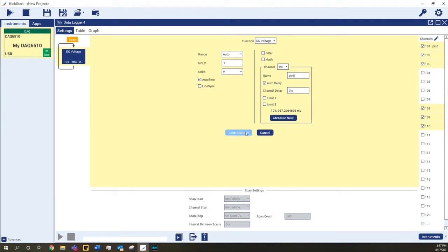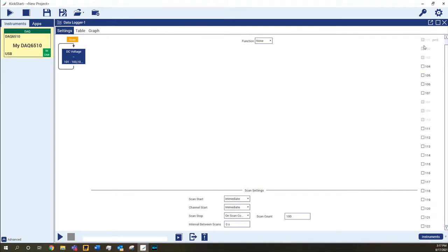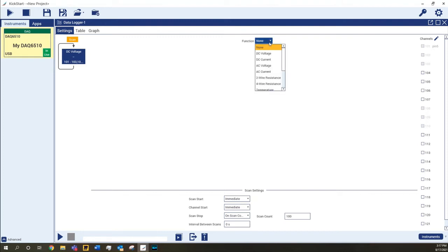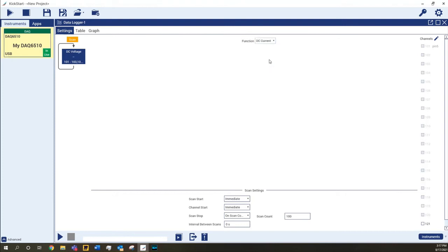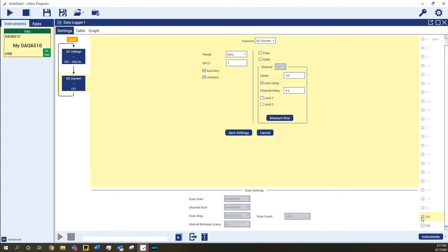Once you've configured the group, save the settings for the configuration, which closes that block. Notice that the configured channels are no longer selectable, as they can only be configured for one measurement at a time. You can configure as many blocks as needed until there are no available channels. If you know what measurement mode you want and you want to quickly select channels for that measurement, select the function first, which will display the available channels for that measurement. They can be selected and configured the same way as before.